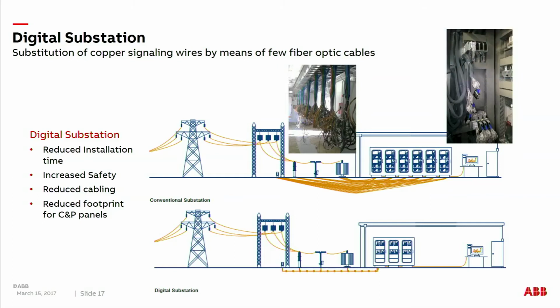You remember I told you about the many connections, the many wires between control and protection and primary equipment, here a transformer, breaker, and so on. Thousands of wires, and this is how it looks in reality. This is just for a medium voltage substation.